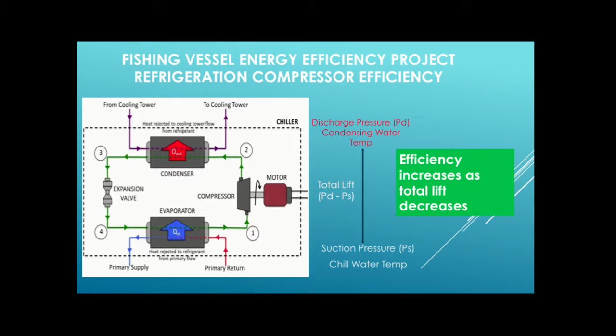What I mean by lift is the difference between the suction pressure of the machine and the discharge. The gas comes into the pump, which is the compressor, at a certain pressure, and then it pumps it up and discharges it at a higher temperature into the ocean to give off the heat. That's what we call the total lift.